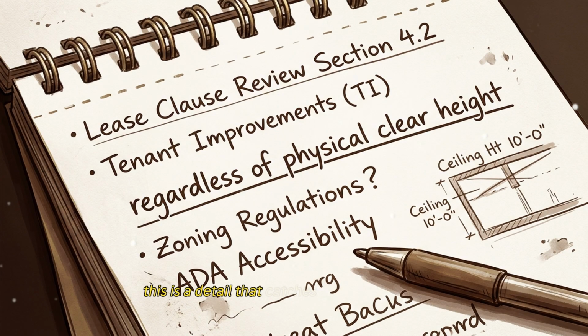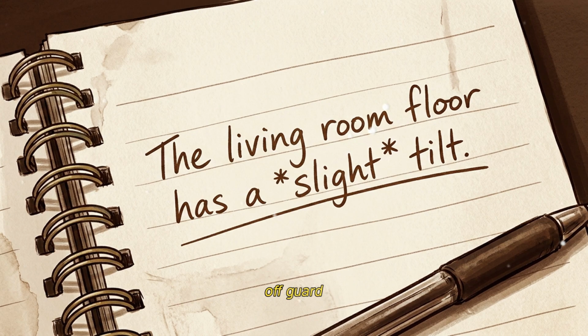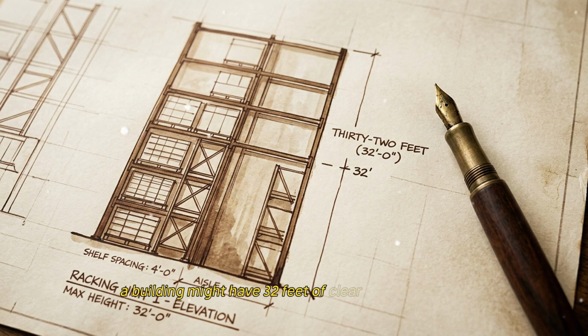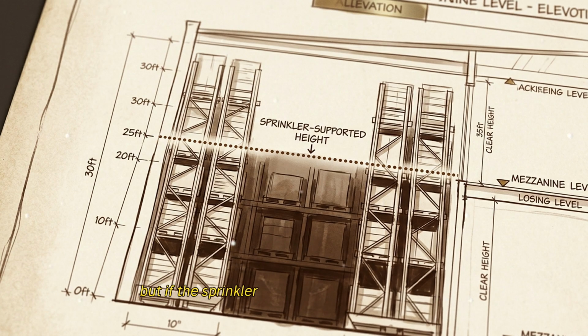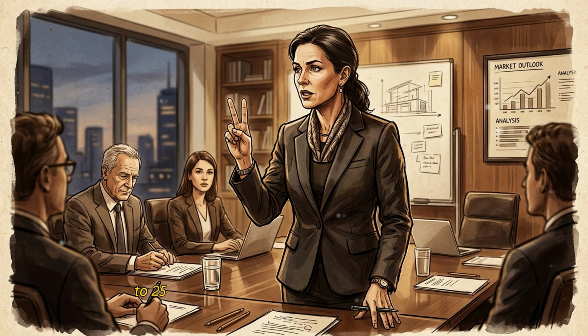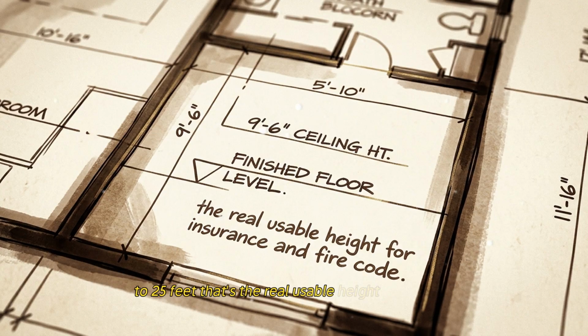This is a detail that catches a lot of newcomers off guard. A building might have 32 feet of clear height on paper, but if the sprinkler system only supports racking to 25 feet, that's the real usable height for a tenant's insurance and fire code compliance.